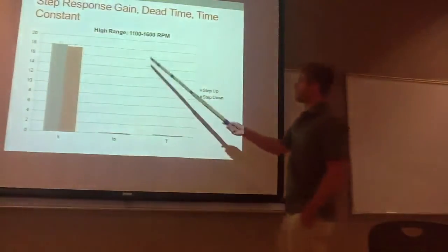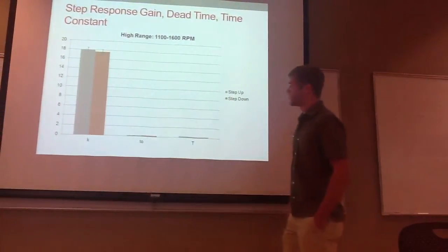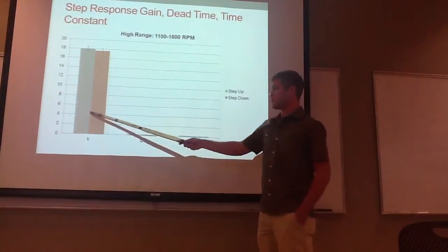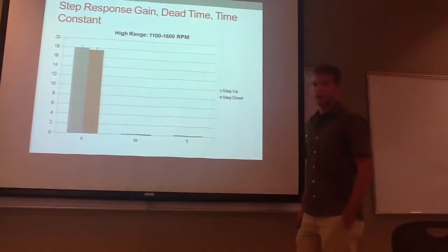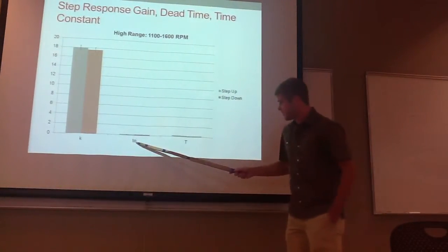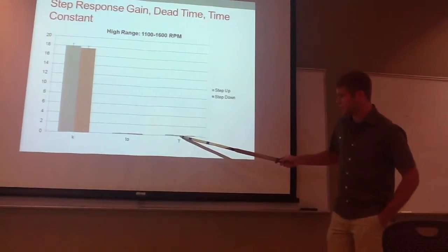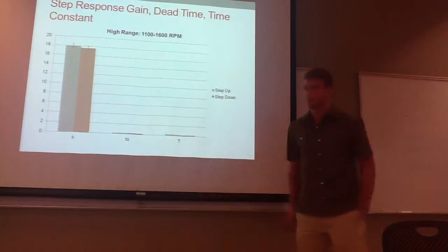And it's the same sort of behavior for our high range of 1100 to 1600 RPM. The same sort of difference in the high gain values, but our dead time and time constants were again very small, with very little difference between the two.